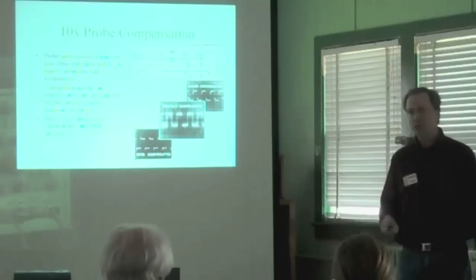Now, because all the scopes have a different amount of capacitance, they're not all the same. They're all 1 megohm resistive, but the capacitive loading of each scope is different. We can't just design one probe that works with every scope from every manufacturer. So that compensation capacitor is made adjustable.